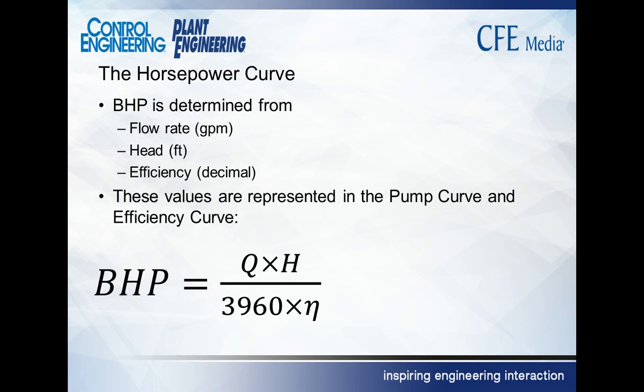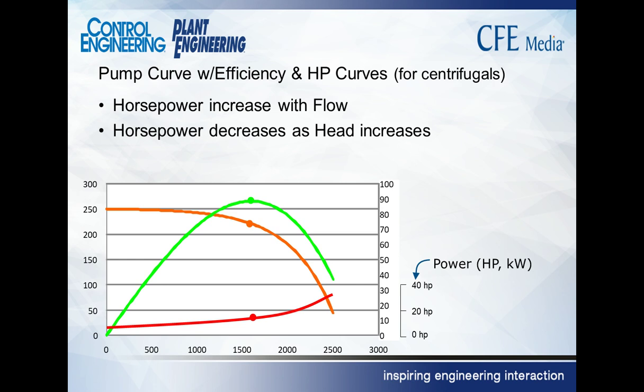If you just take flow times head, flow in gallons per minute, head in feet, and multiply them together and divide by 3960, you've got the gross amount of horsepower represented by the energy that the pump is producing, that it's absorbing. But of course the pump isn't 100% efficient, so when I divide by that efficiency, that eta down there, I then get the net power required. If you're working with pumps, this is a formula that you should know and use frequently.